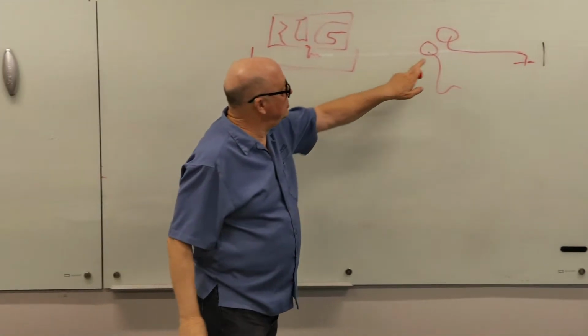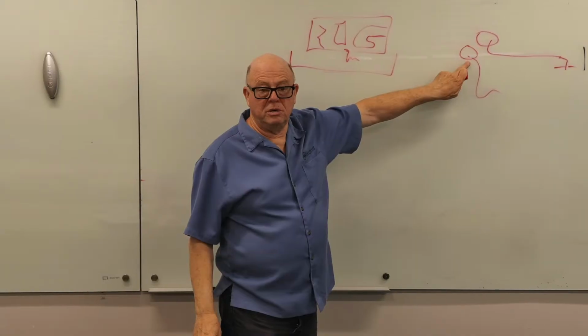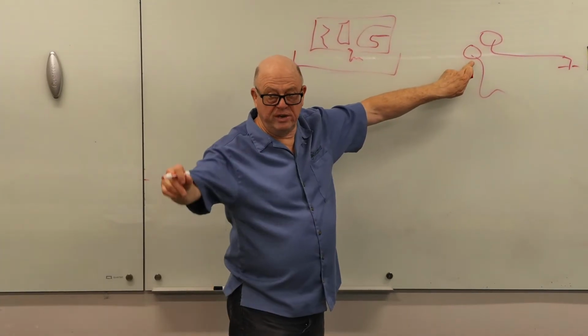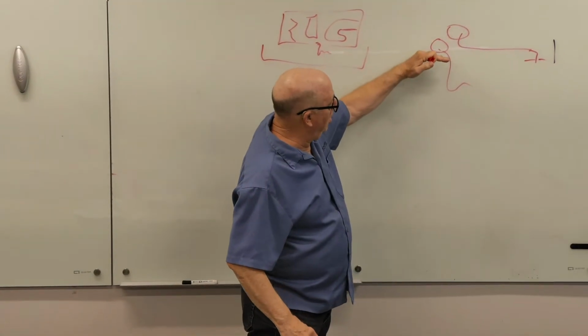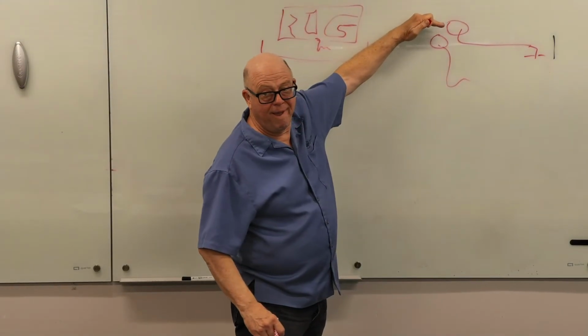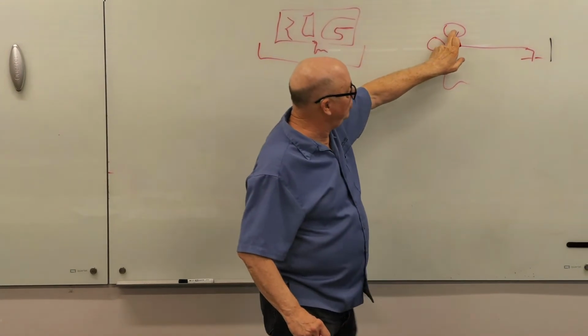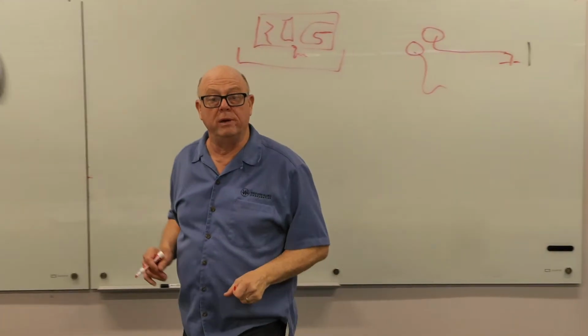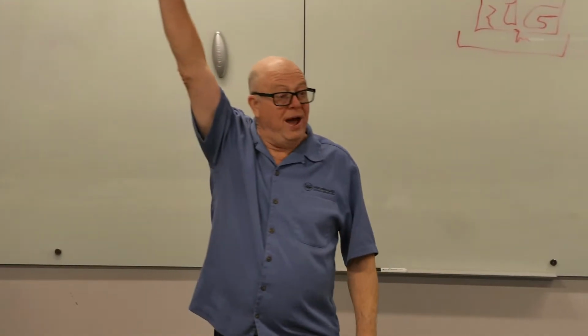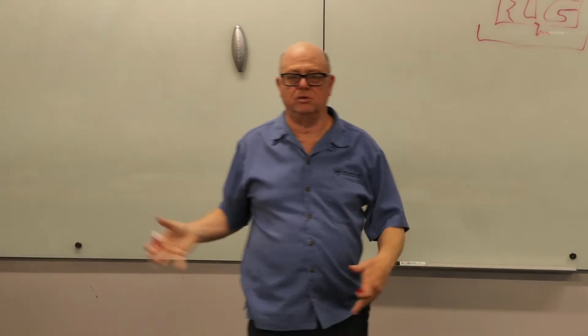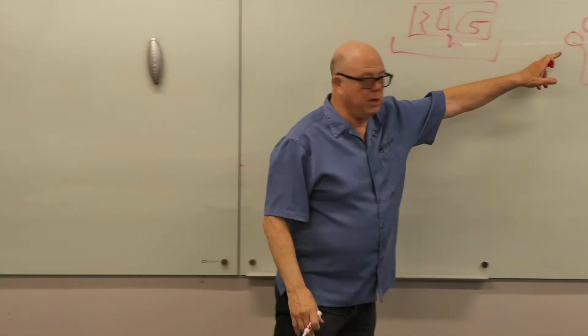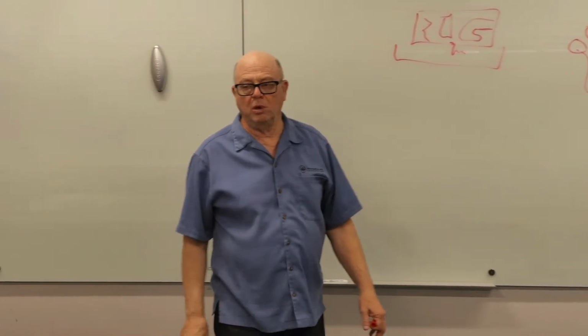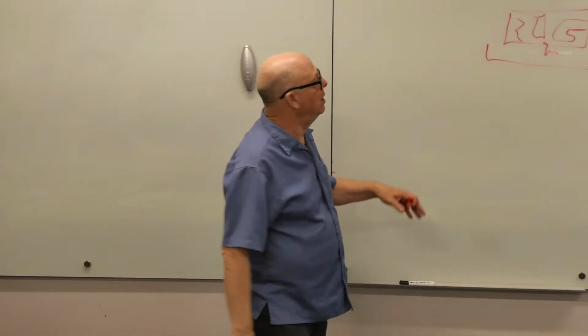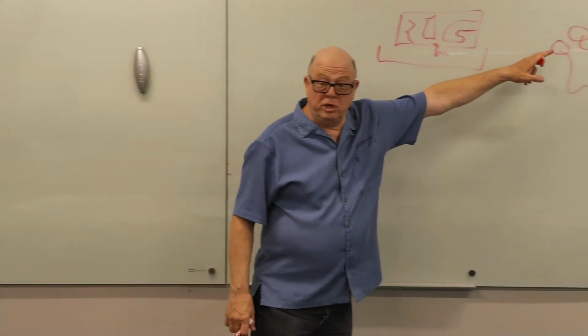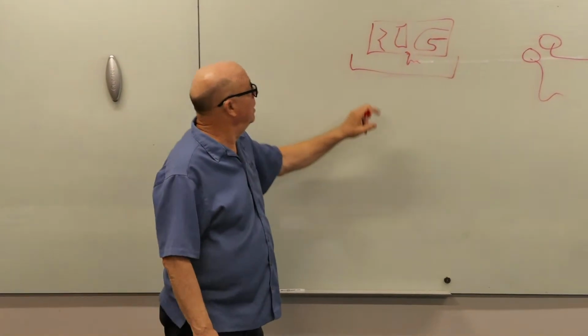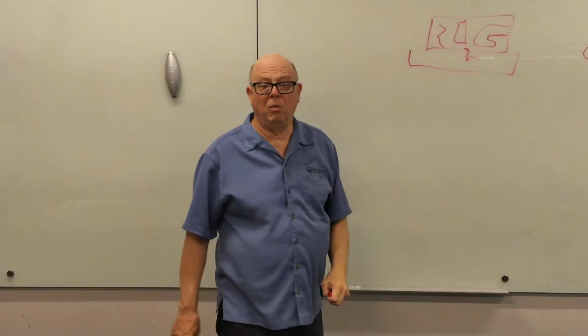So what happens if this drain line plugs? Secondary. The secondary, now the water level rises in the pan, right? And eventually it will come out of this one, and now it'll be dripping out in the hallway. And somebody says, oh, we have a problem, and somebody goes and looks and figures out that you've got a plugged drain line. Drain lines will plug. It's going to happen. So that's a legitimate way to handle it. The pan is a legitimate way.